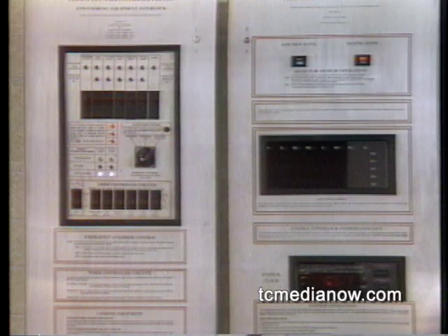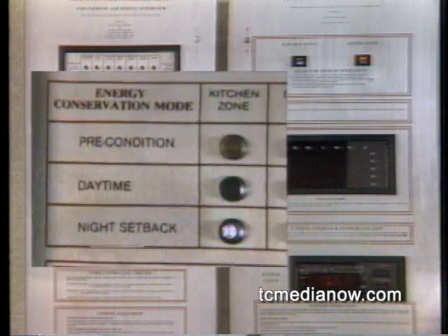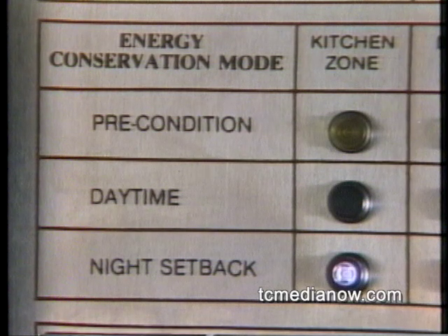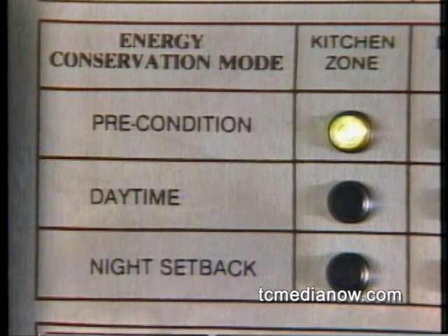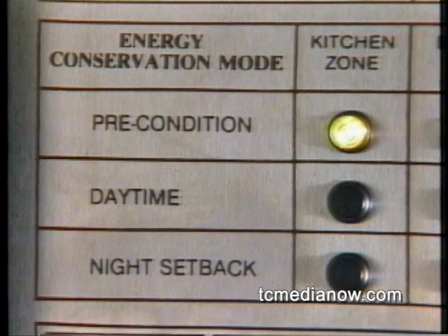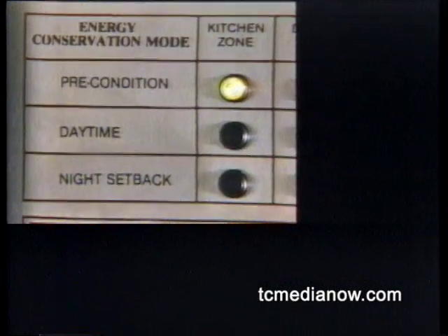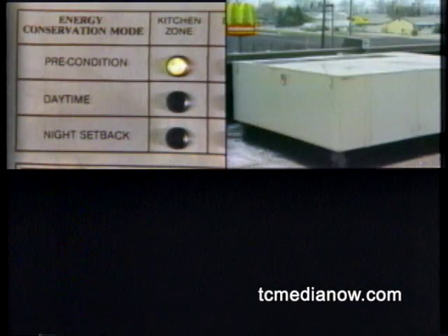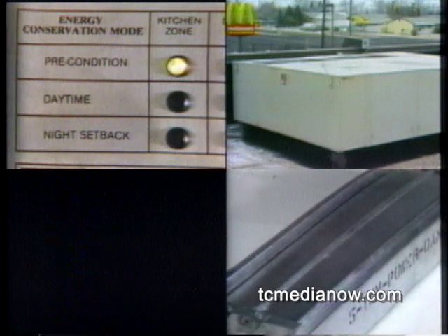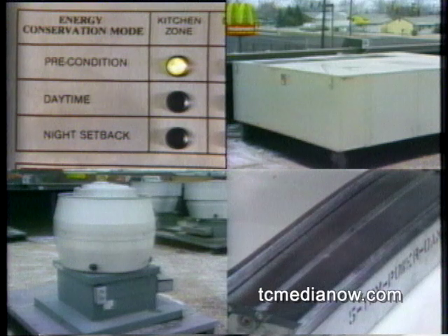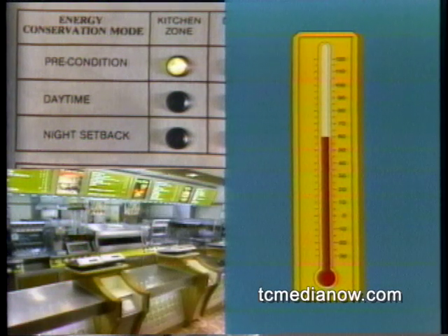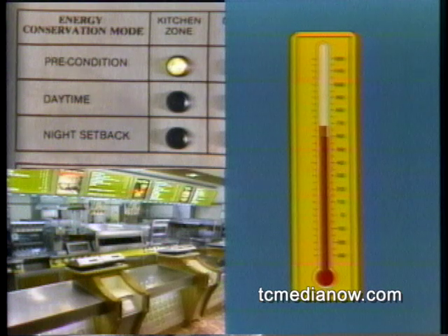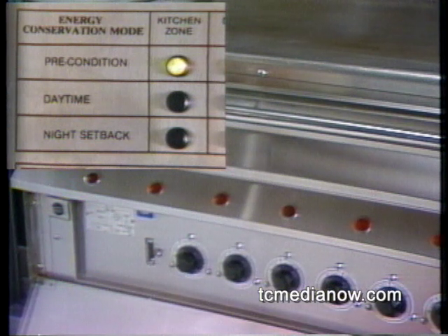The Energy Interlock system provides 3 control modes for energy-using equipment in the store: precondition, daytime, and night setback. The precondition mode is used to bring the store's temperature from night setback to the proper daytime level. It allows only half of each rooftop HVAC unit to function. HVAC outside air dampers remain closed and exhaust fans remain off, so only air presently inside the store must be heated or cooled. The precondition mode brings the store to daytime temperature without setting a demand peak during morning startup. Also, in the precondition mode, power to cooking equipment is off, and that equipment cannot be used.